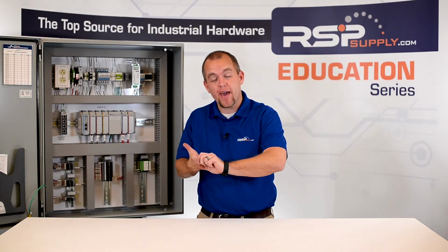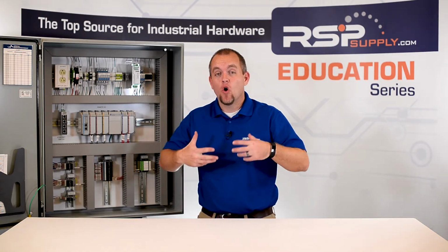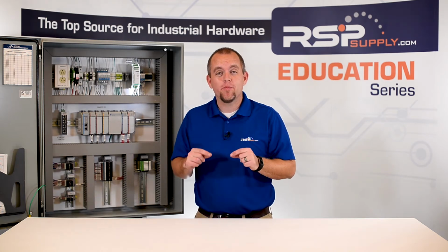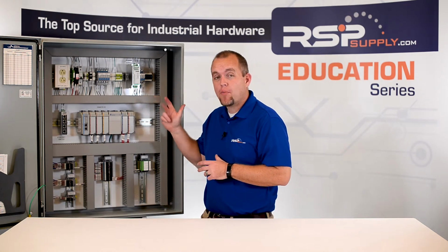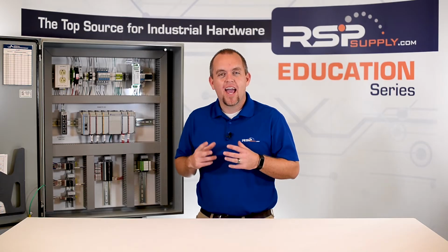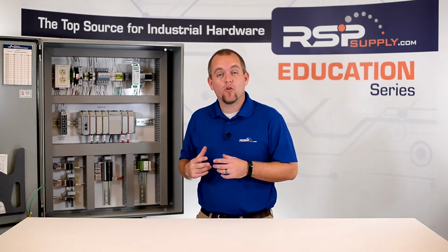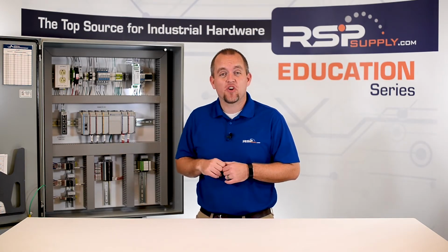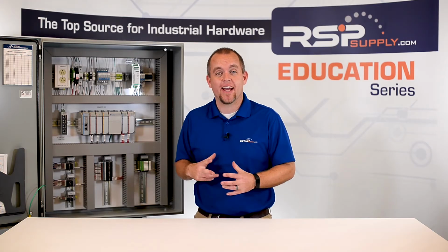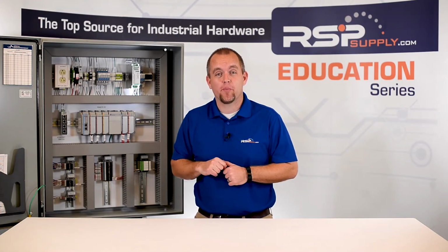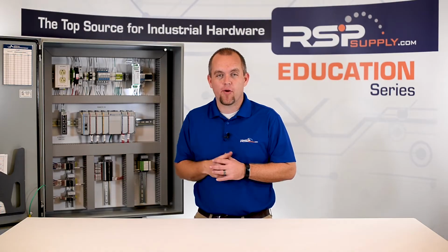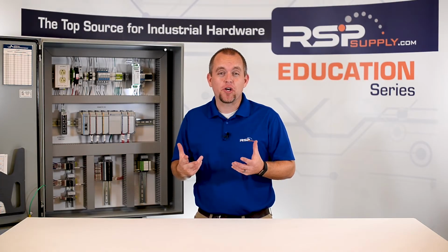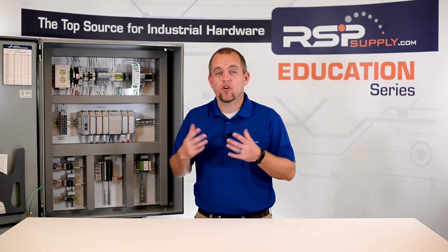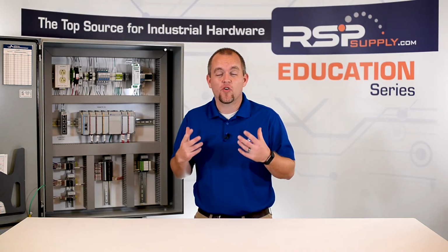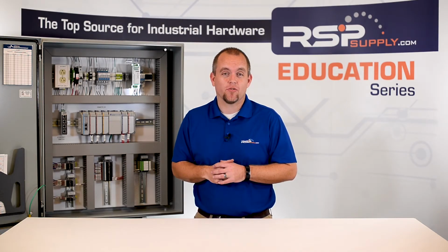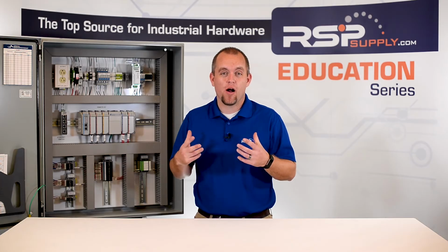Whether it's three phase, 120 single phase, or solar power, we need to make sure that our panel is built properly to handle that kind of power. Any power greater than 120 volts coming into our panel, we need to make sure that we have an external disconnect so that we can disconnect power to the panel before we get in and operate on that panel. It is also a good idea to put an external disconnect on 120 volt power. Again, this just increases the safety level of the industrial control panel and the power that we are operating.